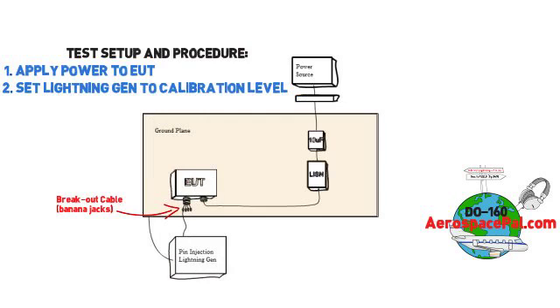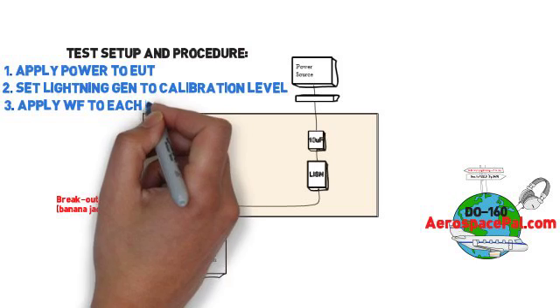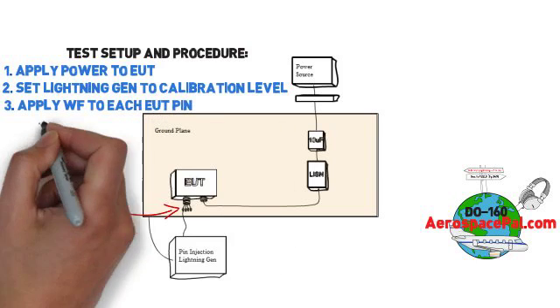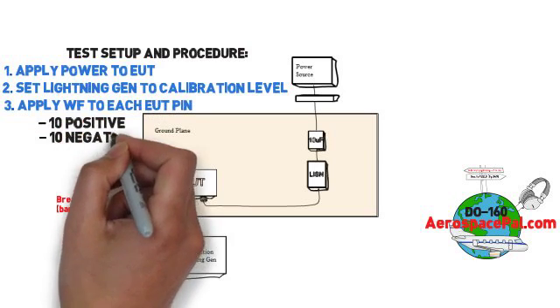This example shows the direct injection method. The test engineer will inject the pre-calibrated waveform and level on each pin 10 times in the positive polarity and 10 times in the negative polarity.